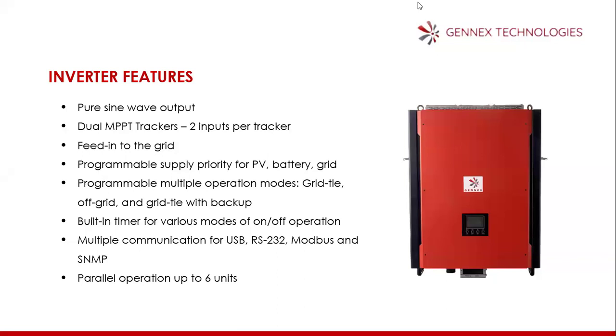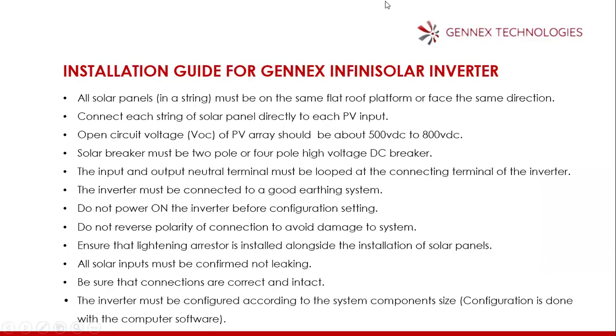Only the newer versions have Wi-Fi built in. Then the inverter can also be paralleled. You can parallel up to 6 units. Remember, each unit is a 10 kilowatt system. So, the installation guide for the Gennex InfiniSolar inverter.